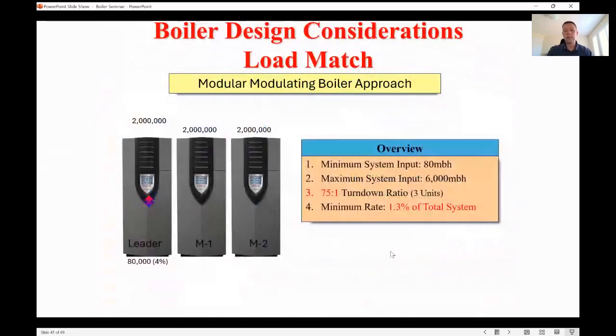So let's take a look at a building. Let's say we have a commercial building here. We have a 6 million BTU load. Well, let's say we size it to load. We have 3 boilers sized to load. So usually I like to do, if one goes down, you can have 60, 65, 66% redundancy, which we're achieving here. And we put in 3 25-to-1 turn down ratio boilers. Well, what's happening here? That gives our overall boiler plant a 75-to-1 turn down ratio.